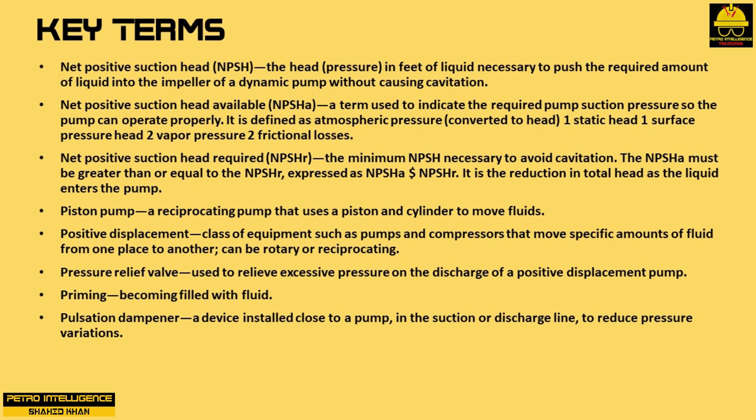Net positive suction head available, NPSHA, is a term used to indicate the required pump suction pressure so the pump can operate properly. It is defined as atmospheric pressure, converted to head, plus static head, plus surface pressure head, minus vapor pressure, minus frictional losses. Net positive suction head required, NPSHR, is the minimum NPSH necessary to avoid cavitation. The NPSHA must be greater than or equal to the NPSHR, expressed as NPSHA ≥ NPSHR. It is the reduction in total head as the liquid enters the pump.